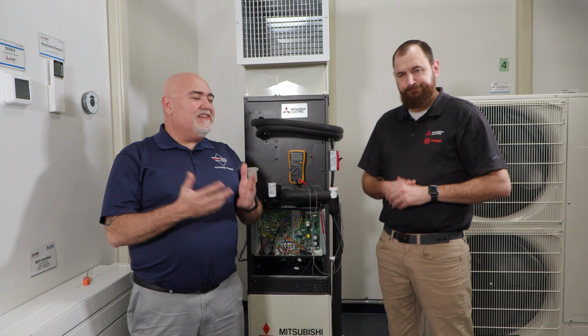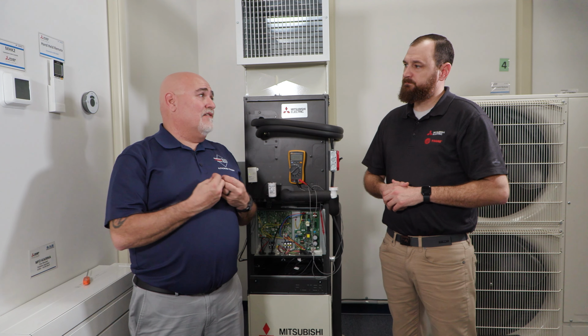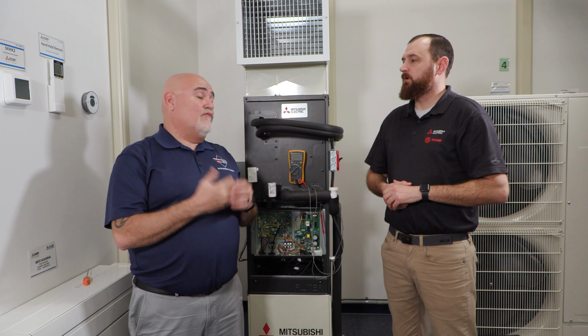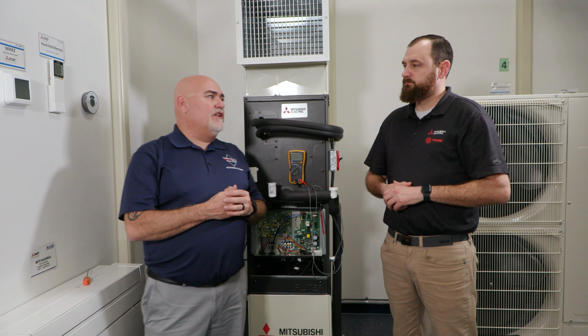And everybody asks, how long do you reset a disconnect for? Basically, we're shutting the power off to that outdoor unit and we're waiting for all the lights to go out. On P-Series, it can be a little bit more tricky. P-Series like to retain their memory. Yes. So this may take up to 10 to 15 minutes sometimes to get rid of that error code. But once that error code is cleared, now we want to do step 2, shut the system off.